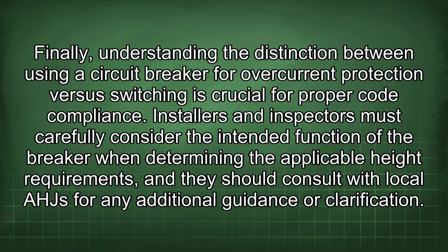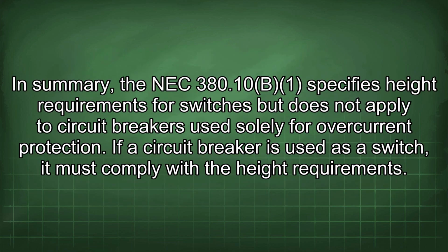Installers and inspectors must carefully consider the intended function of the breaker when determining the applicable height requirements, and they should consult with local AHJ for any additional guidance or clarification. In summary, the NEC 380.10 specifies height requirements for switches but does not apply to circuit breakers used solely for overcurrent protection. If a circuit breaker is used as a switch, it must comply with the height requirements.